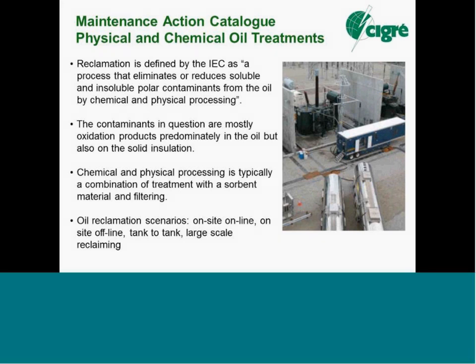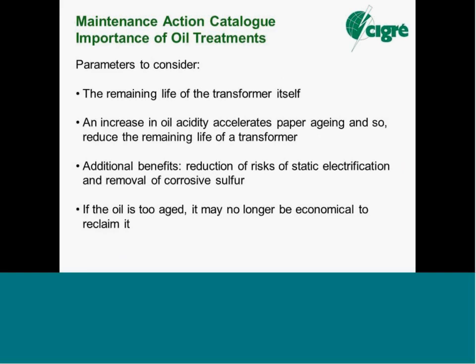So depolymerization is correlated with loss of tensile strength in the paper. If the paper weakens, it's less able to withstand short circuit faults. The more likely it is that there'll be tearing or rupture of the paper insulation, and that a disc-to-disc or turn-to-turn fault may occur in the windings because of the mechanical weakening of the paper.